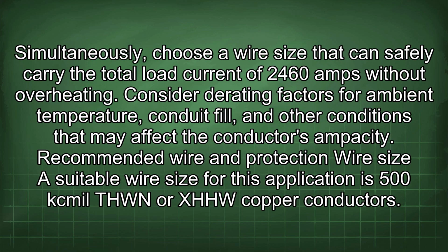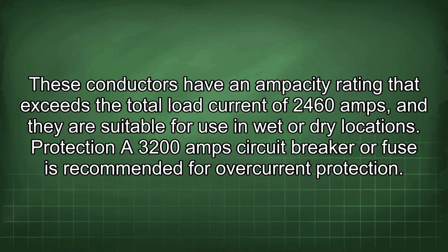Simultaneously, choose a wire size that can safely carry the total load current of 2460 amps without overheating. Consider derating factors for ambient temperature, conduit fill, and other conditions that may affect the conductor's ampacity. Recommended wire and protection. Wire size: a suitable wire size for this application is 500 kcmil THWN or XHHW copper conductors. These conductors have an ampacity rating that exceeds the total load current of 2460 amps, and they are suitable for use in wet or dry locations.